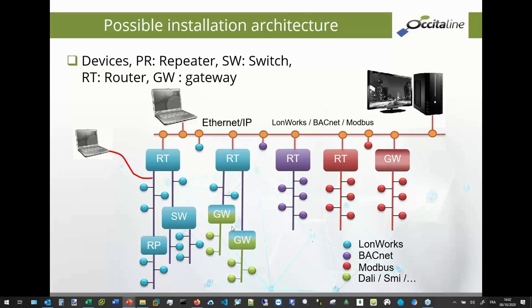In fact, in the field you always have small protocols like DALI, SMI, and so on. These protocols manage only a small number of devices. For example, in DALI for the light you have at maximum 64 devices, but when you have 10 devices with 10 ballasts, it's very good. 10 or 12 devices. And because DALI does not support large addressing, you need a gateway, and this gateway exists with a field protocol in DALI and probably a field protocol in BACnet, in Modbus, in whatever you want. The router can manage different protocols.